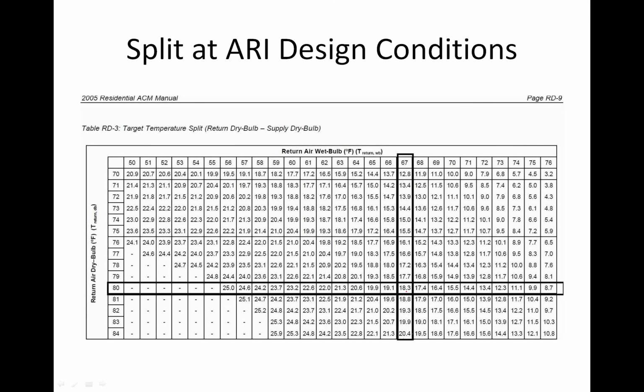But you can see what happens is as the wet bulb goes down, so if we go from 18.3, which is right here, we're at the center, 18.3. If we drop that wet bulb down to 59, well, now the temperature drop across the evaporator goes from 18 to 23 degrees. And the reason it changes is more energy is going into dropping the temperature now because there's less humidity to deal with. Remember, wet bulb takes into account heat and humidity. So as the humidity drops, the temperature drop across the coil will increase, because now as the humidity drops, more energy is going to dropping the temperature than it is removing humidity.